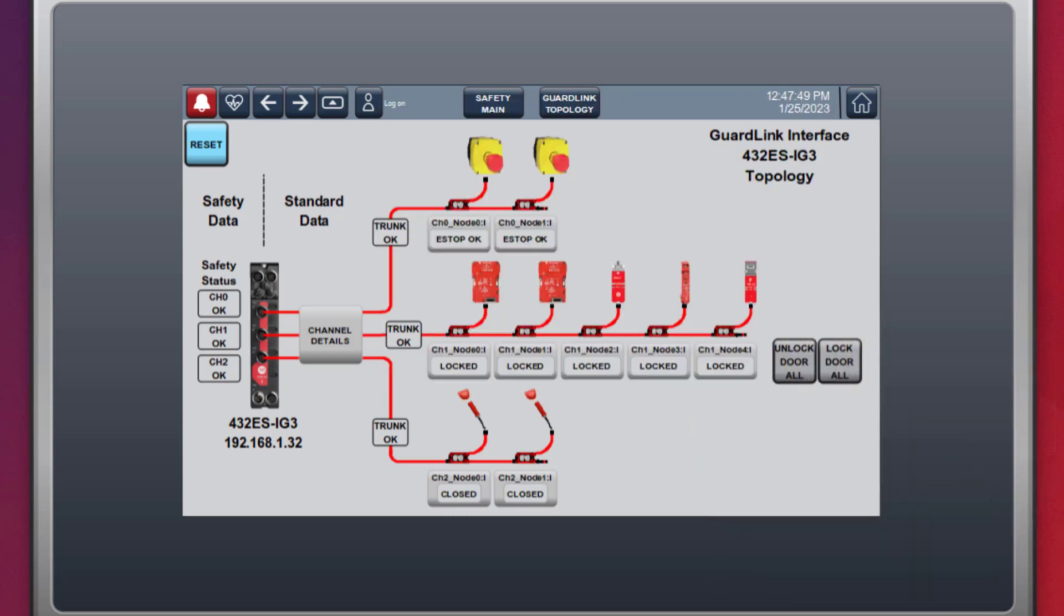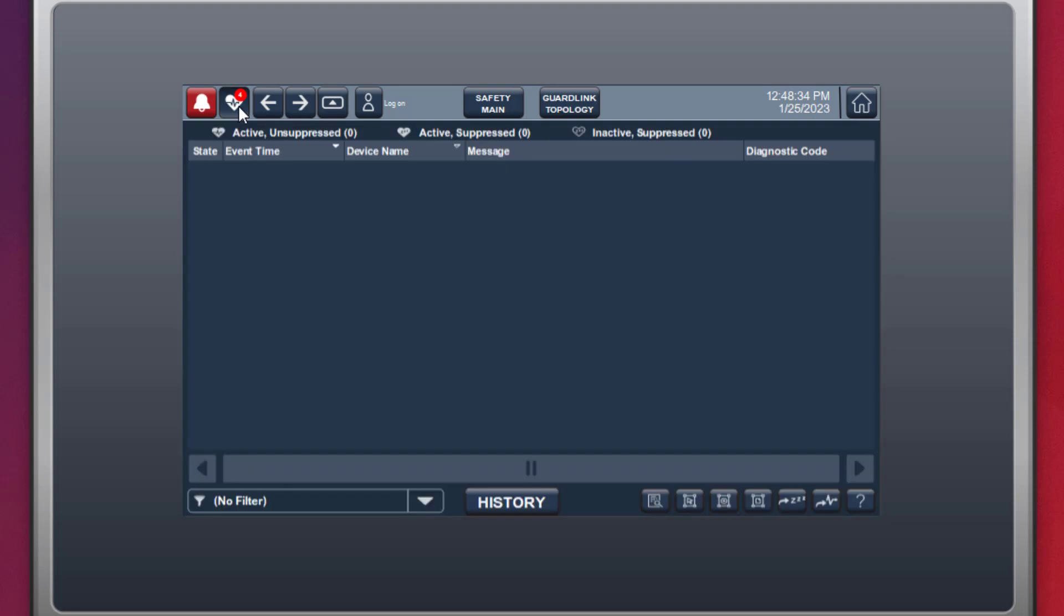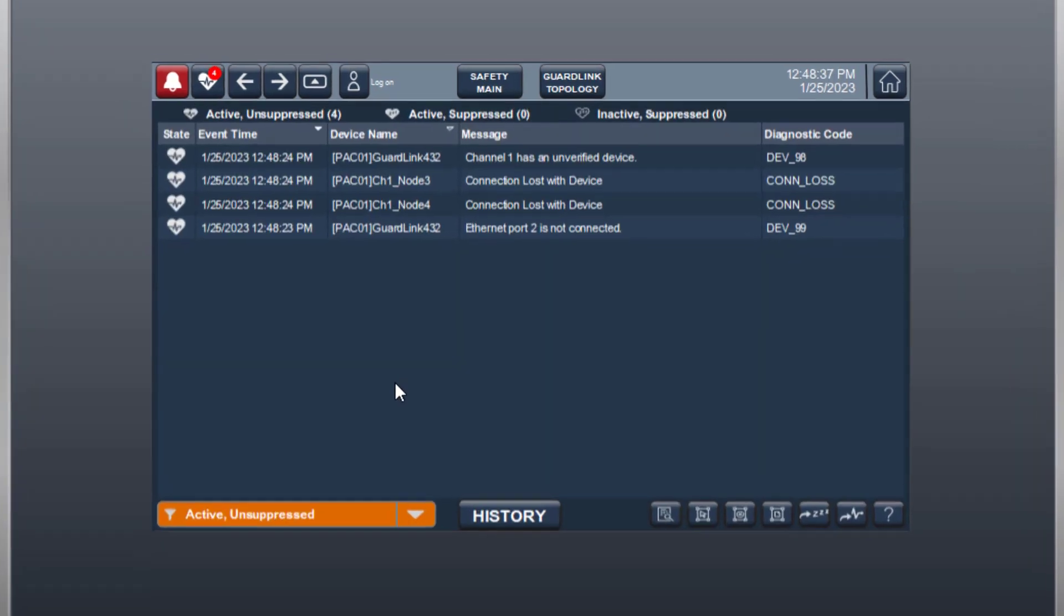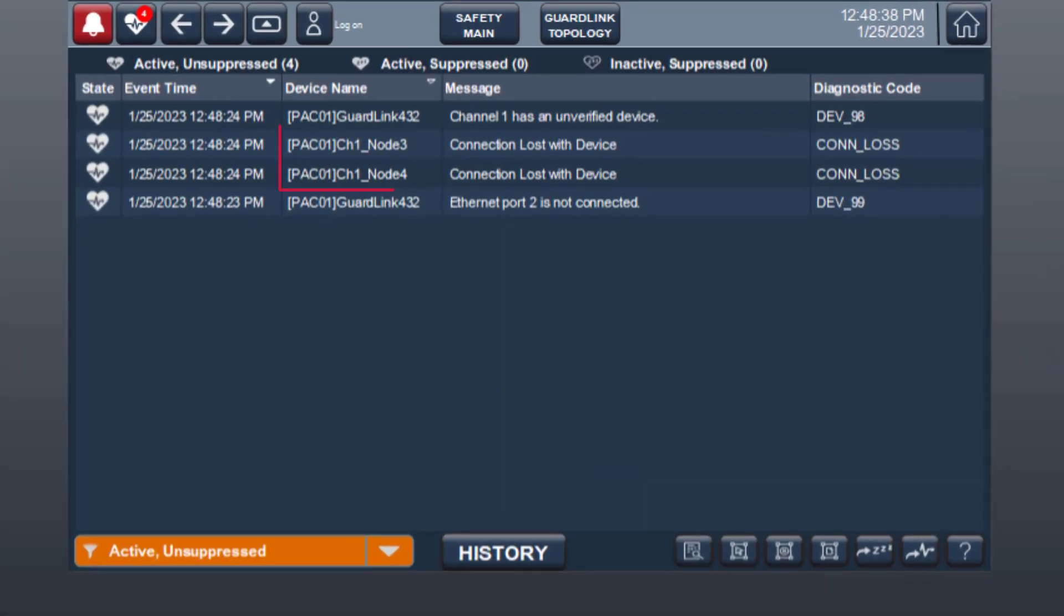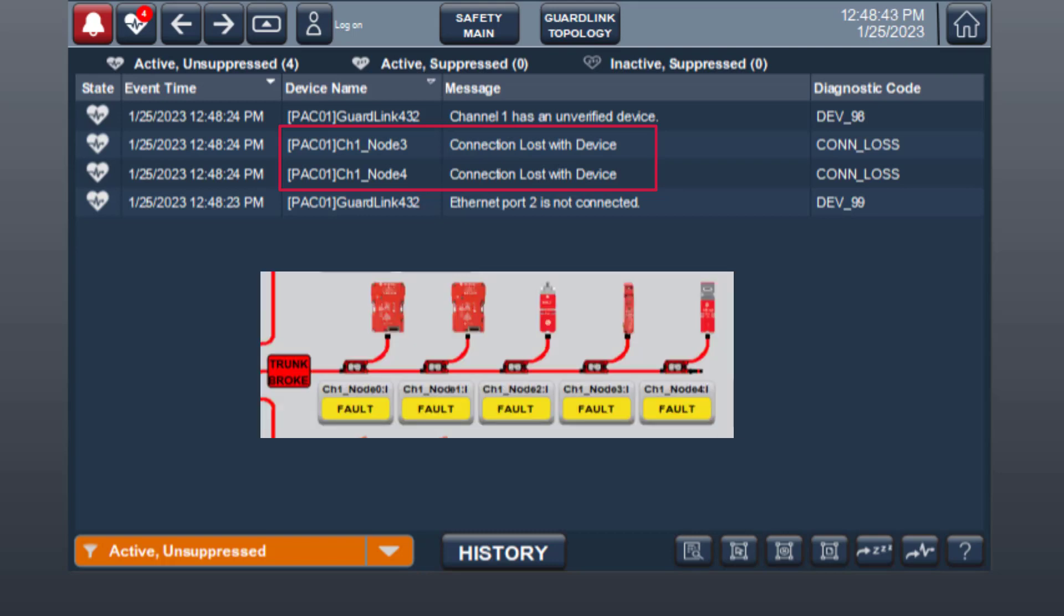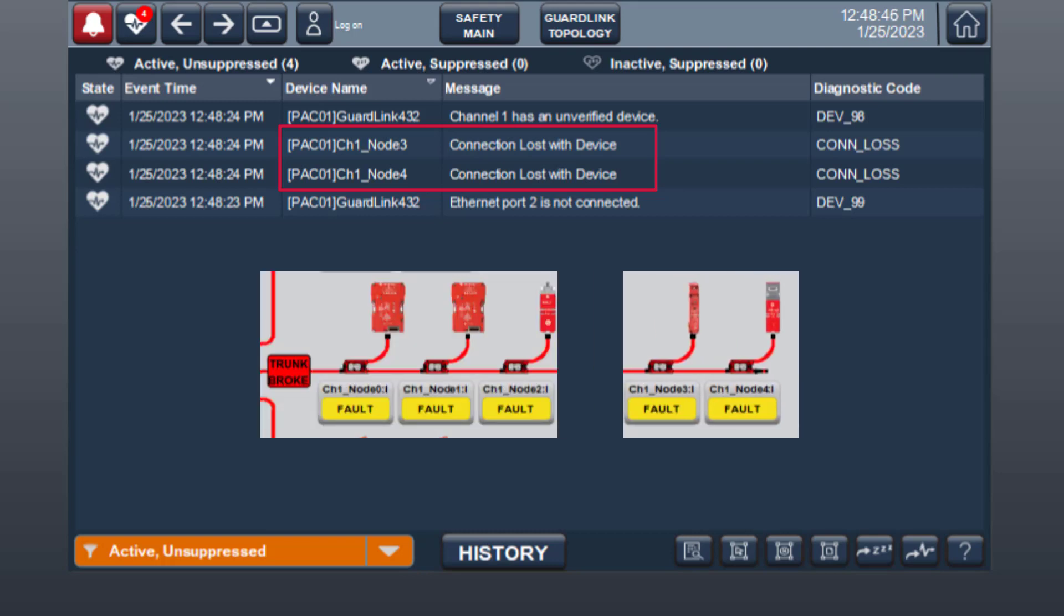Unplugging the channel 1 trunk cable, the GuardLink interface detects a broken GuardLink trunk. The automatic diagnostic features indicate that node 3 and node 4 lost connection. With no programming, the user can pinpoint the broken trunk to between node 2, which is still connected, and node 3, which has lost connection.